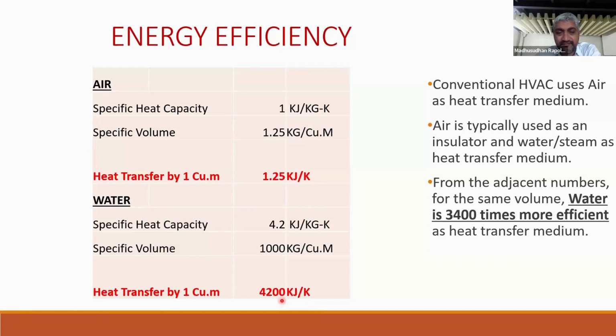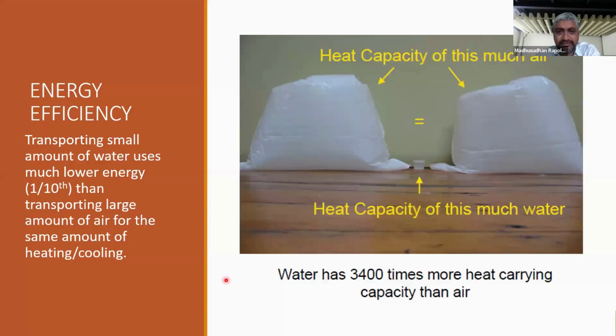And the second reason is we are not using air as a means of heat transfer, because if you compare the heat transfer by 1 cubic meter of air versus 1 cubic meter of water, there's a factor of almost 3,400. That is a big difference. So the transport energy that is required to provide 1 ton of cooling would be way higher if you were to use air, because you require a lot more volume of air than the transport energy that is required when you use water. So these are 2 reasons why radiant cooling provides anywhere between 30 to 50% energy savings in cooling, depending on what you're comparing it to, right?